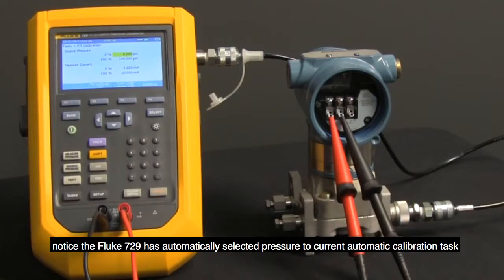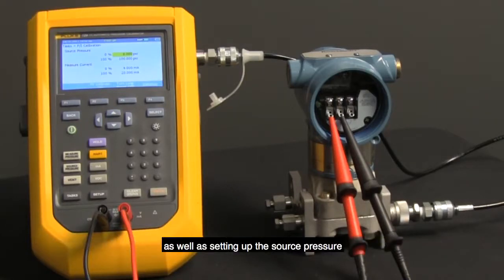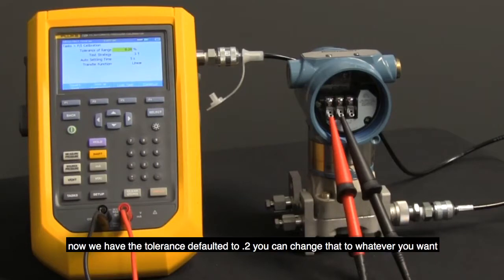Notice the Fluke 729 has automatically selected the pressure to current calibration task, as well as setting up the source pressure and 4-20 output. So we know that it's 0 to 100 psi. Press F4 to continue. Now we have the tolerance defaulted to 0.2. You can change that to whatever you want.